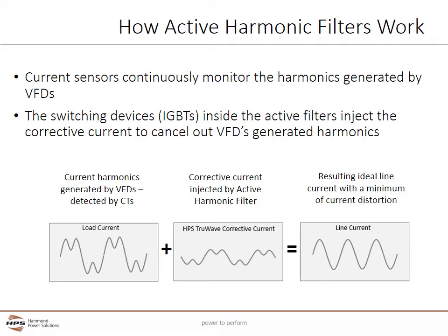Here is a diagram of how an active harmonic filter works. The unit uses highly accurate current sensors to continuously monitor the current harmonics and instantly creates the current flow from its IGBT-based output module to make the resulting line current harmonic-free, balanced, and at unity power factor. Note that while an active harmonic filter can correct for power factor, it is often much more economical to create better power factor using capacitors. Active harmonic filters are often necessary to protect power factor correction capacitors from overheating, since those capacitors attract current harmonics which can damage and destroy them if not mitigated.